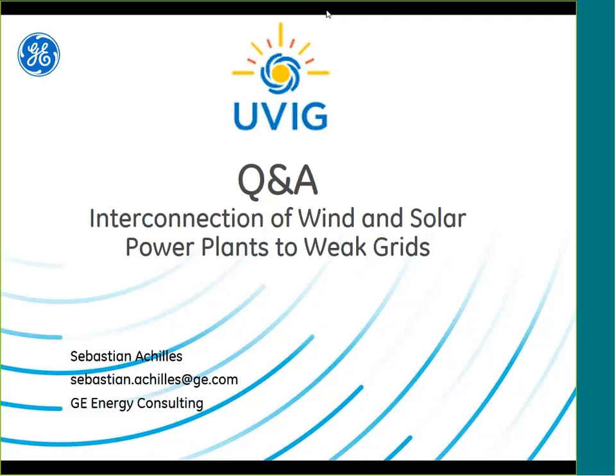When you have an islanded system and want to use the type of solar and wind controls normally used in the industry, you'll need some other source that provides system strength. In offshore systems, that's a converter that operates like a voltage source. In other systems, it could be a synchronous condenser. You will need something that provides system strength if you're using the standard products for PV and wind to solve the problems we discussed today.